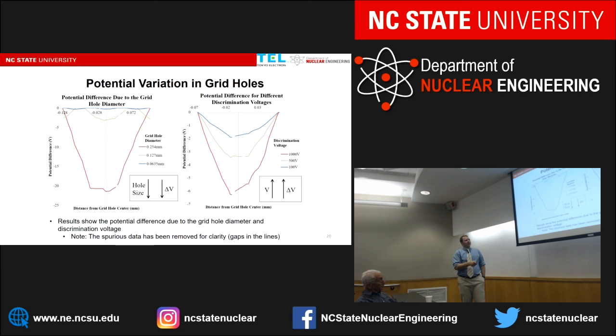And then the last interesting one was to look at the discrimination potential again, because we're scanning the discrimination grid, so what does that do to the holes? And what we found is that as you increase the potential applied to the discrimination grid, the potential difference increases, which is a problem because we cannot fix that. We have to apply the potential, meaning the higher potentials we go, the worse this is going to get. So this is kind of a limiting factor on our energy resolution.